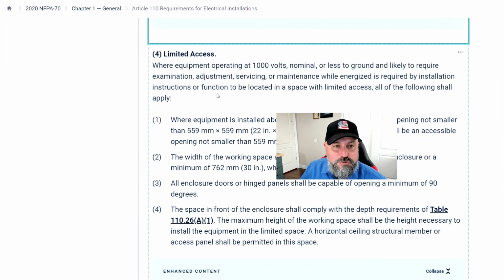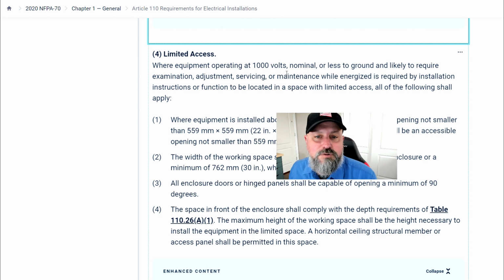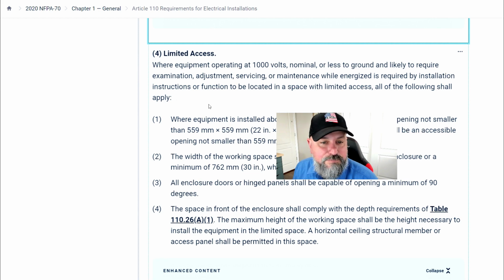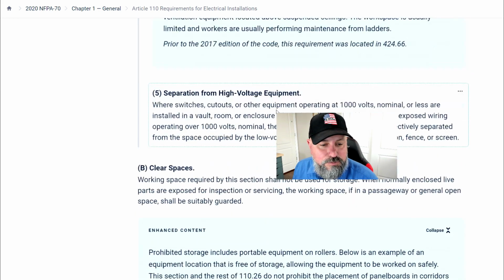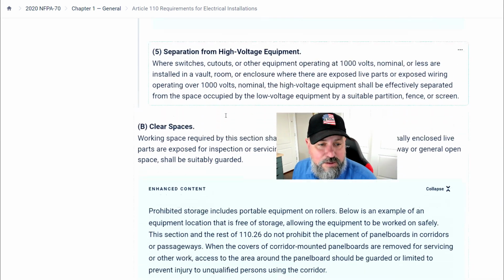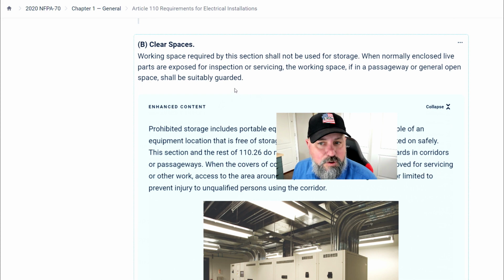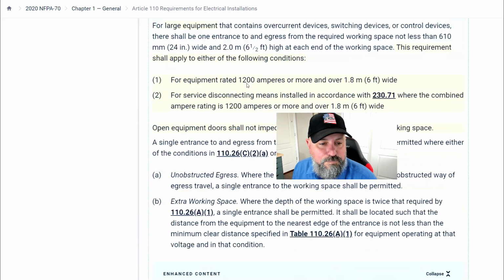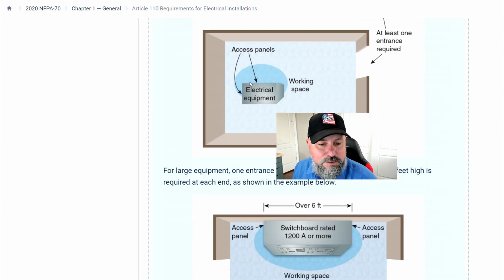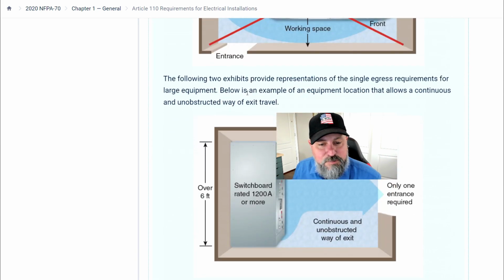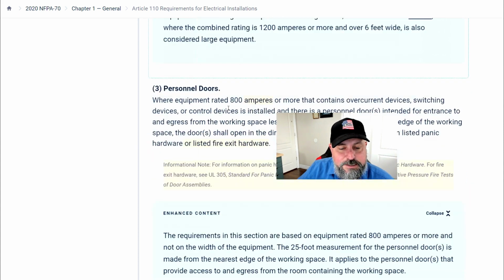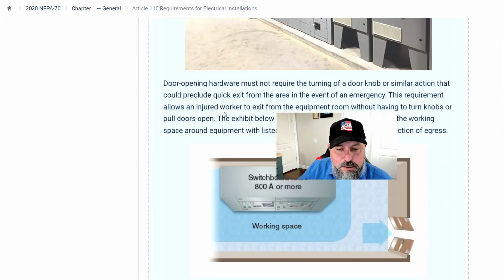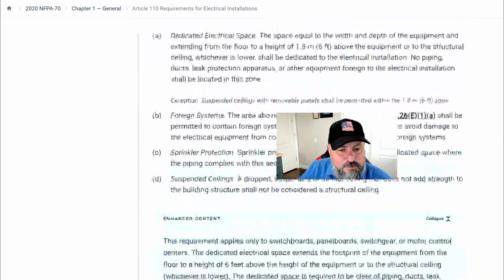So the next one I want to go into is limited access. Where equipment operating at 1,000 volts nominal or less, likely to require examination, adjustment, servicing, or maintenance while energized, is required by installation instructions or function to be located in a space with limited access, all of the following shall apply. Actually, the one I really wanted to go into, because you're probably not going to be working on the 1,000 volts, but you could be, but I don't think that one's as important right now, is the space above. Because this is something you're going to deal with when other trades come in and put their stuff above our switchboard, our switchgear and everything. So let's get to that.